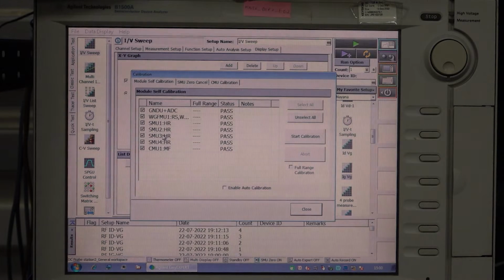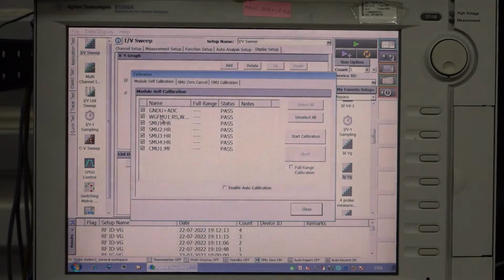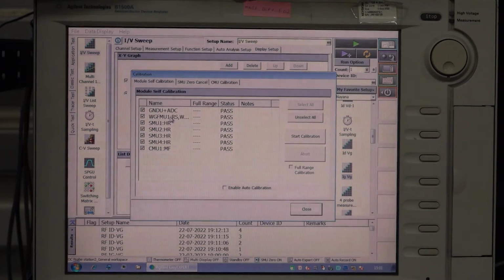So basically the source measuring unit whatever we have, it is capable of applying plus or minus 100 volts and plus or minus 100 milliamps of maximum current. So the resolution of these 4 SMUs are 10 picoamps and 100 microvolt. So we have a capacitance measurement unit. We can apply plus or minus 100 volts and AC voltage is 25 millivolts to 250 millivolts maximum and the frequency is 1 kilo to 5 megahertz. We have a fast waveform generation measurement unit. We can apply pulses which is 10 nanoseconds to 1 second of sampling rate using this unit.